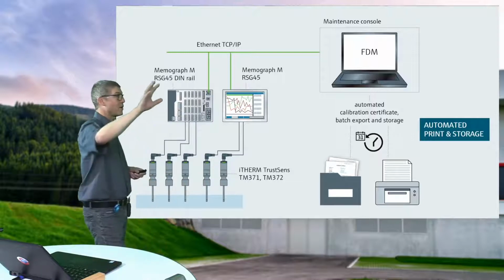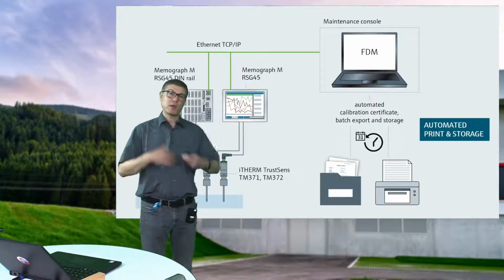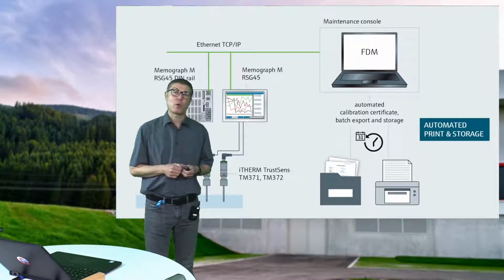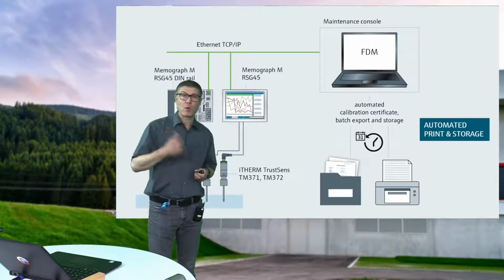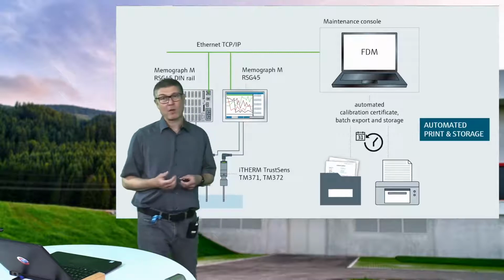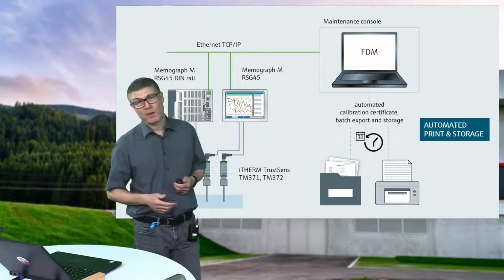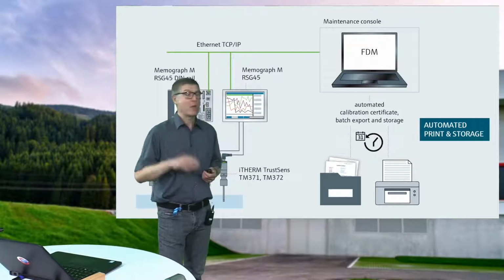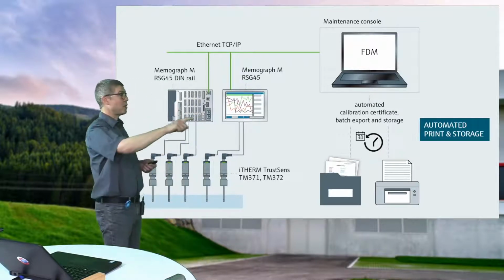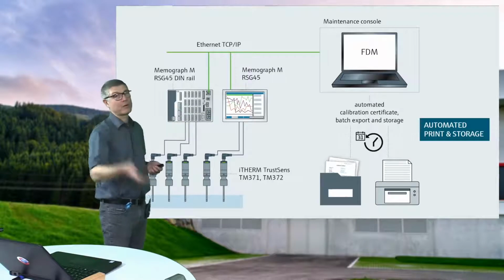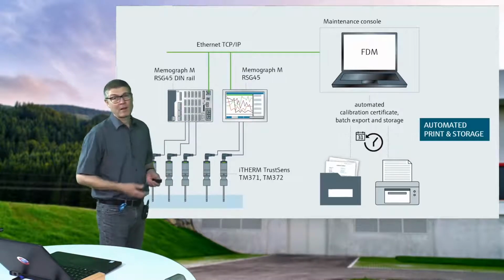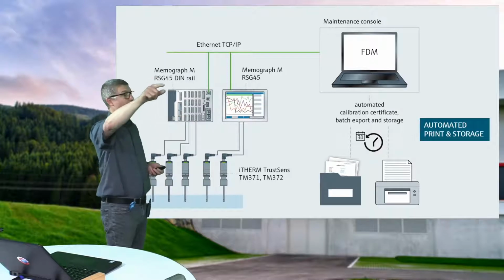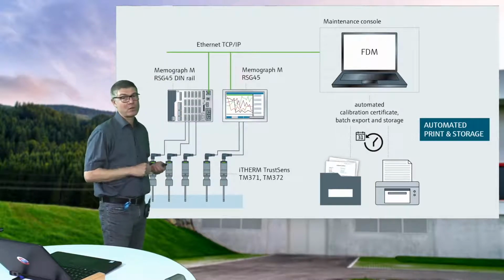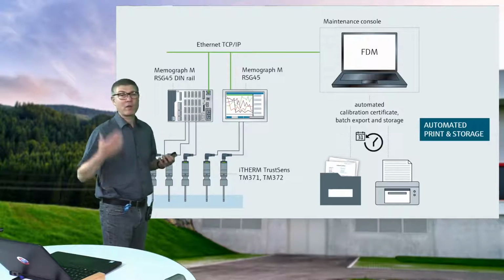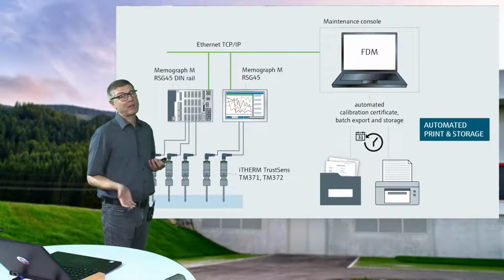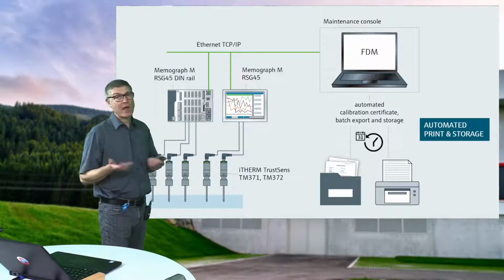This is also a kind of link between the automation instrumentation world and the quality managers. Because usually when a quality manager wants to have a certificate of the last calibration, he's going to the instrument people and says, please give it to me. And here, using this chain, we have the connection to the process control system, to control loops and so on, and going via the IP connection, we go to the file server. And so the quality guy can have access to the calibration records without asking somebody.